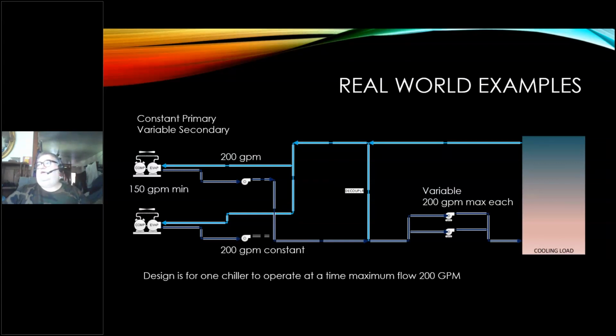I can't do that. So they put this decoupler in so I can run 200 GPM constantly on that loop. I'll pump that water into the secondary loop, where I run one of the variable speed pumps up to 200 according to my load, and it comes back at 200 GPM. If I'm at full load, all 200 GPM come back to the chiller. Perfect. Works great. However, if I've got 40-degree water going out and 50-degree water coming back, this is where my ideal condition is.